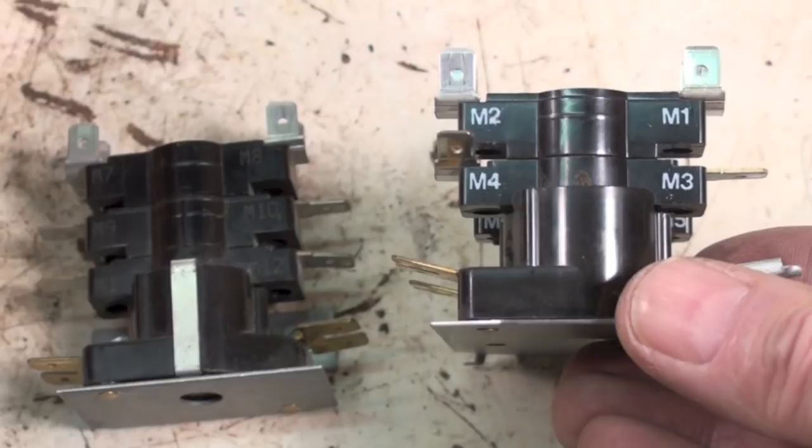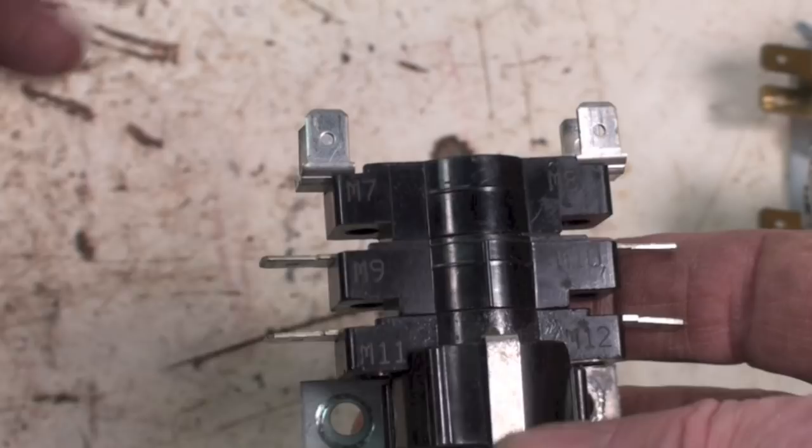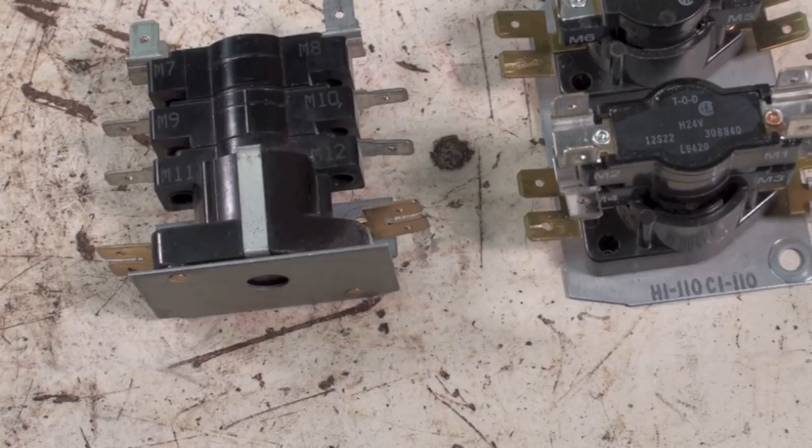So when M1 and M2 close, the fan starts, the first element comes on, then a little later, three and four, five and six, seven and eight, nine and ten, eleven and twelve. That would be the sequence that they come on.